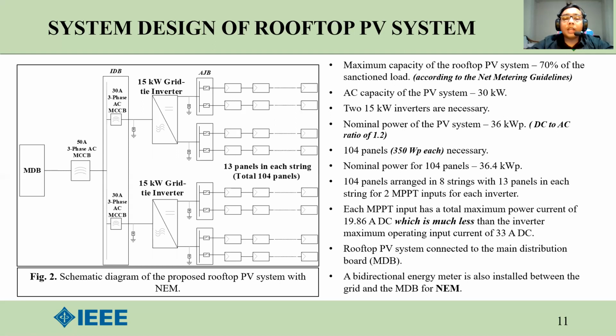So according to the net metering guidelines, the PV system size can be 70% of the sanctioned load, which stands at 30 kilowatt. So we would need two 15 kilowatt inverters, and using a DC to AC ratio of 1.2, the nominal power of the PV system is 36 kilowatt peak. And using 350 watt peak panels for the 36 kilowatt peak PV system, we would need 104 panels. The 104 panels are arranged in 8 strings with 13 panels in each string. In each MPPT input of each inverter, two strings are connected. Also, a bidirectional energy meter is installed between the MDB and the grid for net metering.